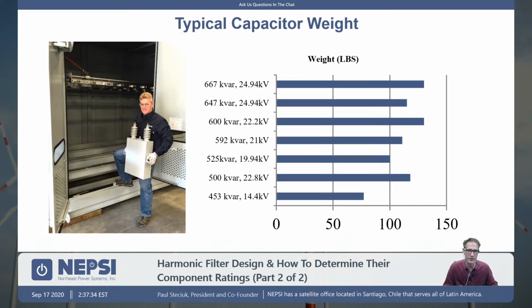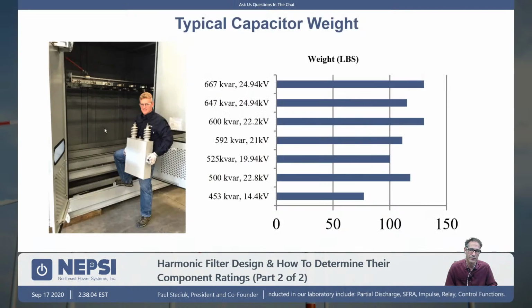We have a philosophy, we like to go with larger, heavier cans and try to minimize. The whole purpose of a metal-enclosed system is to reduce the size of the equipment, so don't be afraid of specifying a higher rated capacitor can. It helps to shrink the size of that metal-enclosed system down, and that's really one of the key advantages of the metal-enclosed system, decrease the size of the system. So we're up in this 100 to 150 pound range, but really for a metal-enclosed solution, you're able to pick that capacitor up and bring it in and set it into the enclosure.